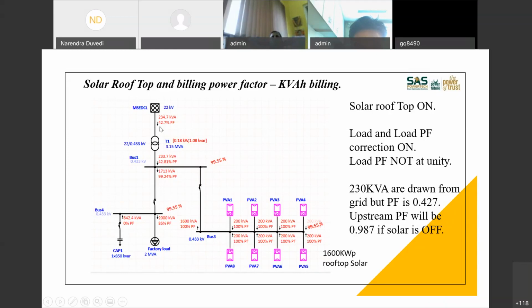Here the entire balance reactive power I have to take from the grid, and I am taking very little active power from the grid because my solar is on. You can see it here, my solar is on. So 1600 kVA of the total requirement is fed by solar. It is not taken from the grid, but the balance reactive power is now taken from the grid. This is the reason your power factor will go low. So unless this is compensated properly, your power factor can still go low. This is possible.